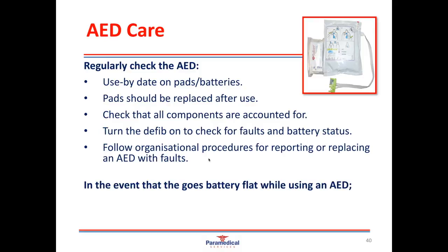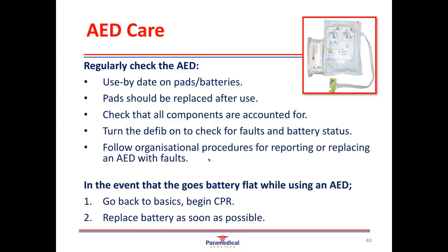Regularly check the AED to ensure pads and batteries are in date. Replace pads after use as they are single-use. Check that all components are accounted for. Turn on the AED to check for faults and battery status. Follow your organizational procedures for reporting or replacing faults. If the battery goes flat, continue CPR and call for another AED to be made available, and replace the battery as soon as possible.